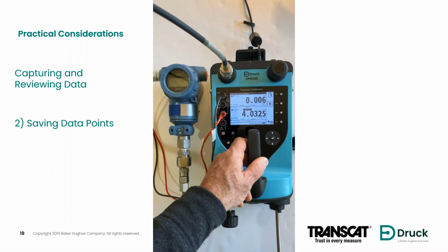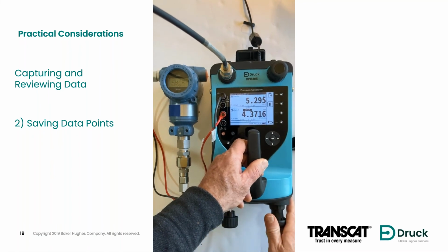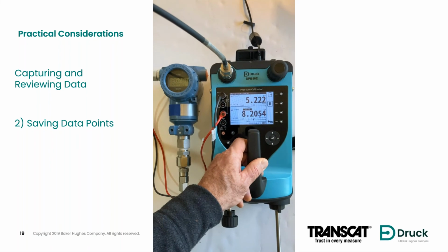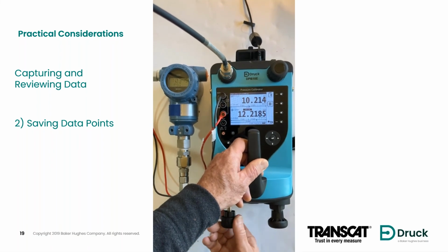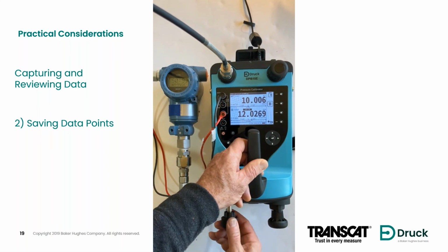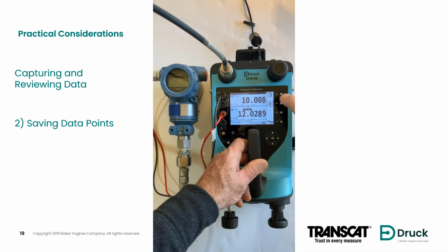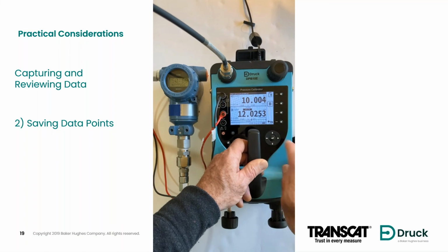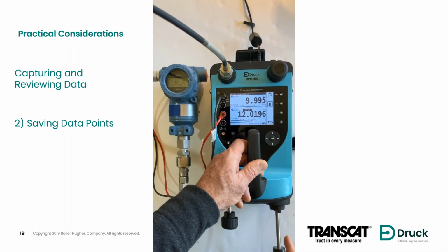Now I'm generating pressure to go to the first point that it's telling me to, which I believe will be 10 psi. I'll let it settle out for a second, make some small adjustment, and then take the second point. Don't worry, I've only got a couple more points. I didn't do a 10-point up and down calibration for this video. So good enough, take the point. Yes, do you want to take it? Yes, I do. Save it, go to the next one. 20 psi for the next one, which is the full scale.